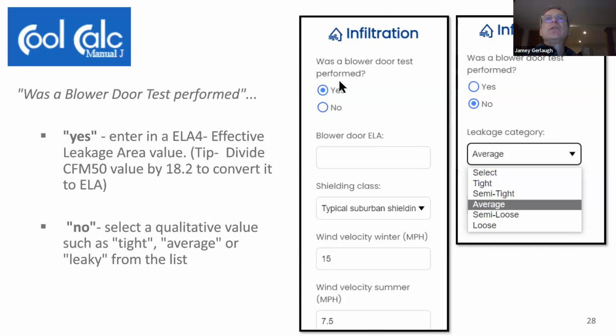So it asks, was a blower door test performed? If you say yes, and you have an ELA - which is, oh my gosh Leland, what is that, I know it's like equivalent leak area, I think I got it right - that's the equivalent hole size that you have in your house. I've got a tip here that says if you've got a CFM 50 number, you can just divide by 18.2, and that will give you your ELA number, so you can enter that in there. You can also adjust the wind velocity and things like that.